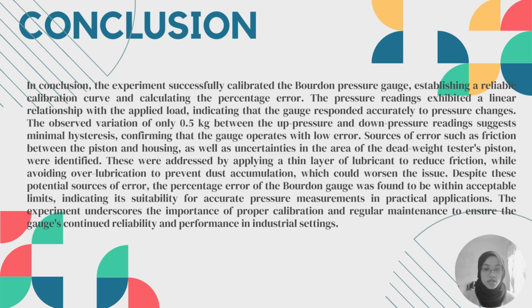Sources of error such as friction between the piston and housing, as well as uncertainty in the area of the dead weight tester piston, were identified. These were addressed by applying a thin layer of lubricant to reduce friction, while avoiding over-lubrication to prevent dust accumulation, which could worsen the issue. Despite these potential sources of error, the percentage error of the Bourdon gauge was found within acceptable limits, indicating it is suitable for accurate pressure measurement in practical application. The experiment underscores the importance of proper calibration and regular maintenance to ensure the gauge continues to be reliable and perform in industry settings.